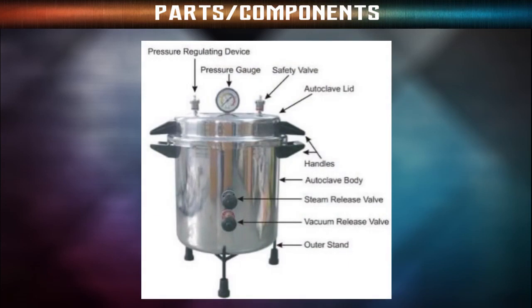Coming to the parts and components, first is the pressure chamber. The pressure chamber is the main component of a steam autoclave consisting of an inner chamber and an outer jacket. The inner chamber is made up of stainless steel and gunmetal, which is present inside the outer chamber made up of iron case. The autoclave used in healthcare laboratories has an outer jacket that is filled with steam to reduce the time taken to reach the sterilization temperature. The inner chamber is the case where the materials to be sterilized are put. The size of the pressure chamber ranges from 100 liter to 3000 liter.